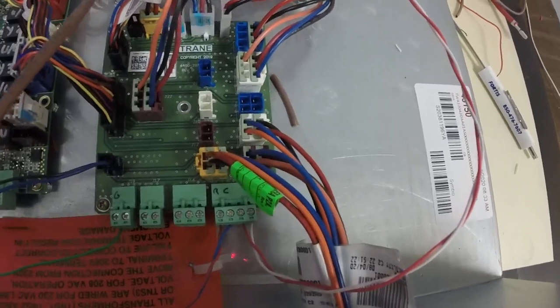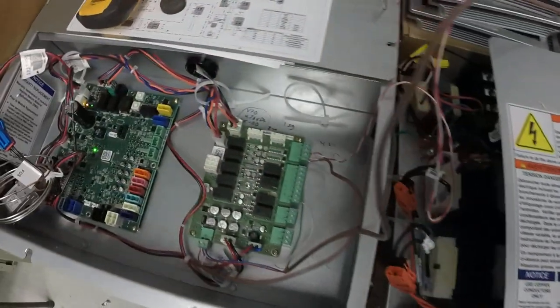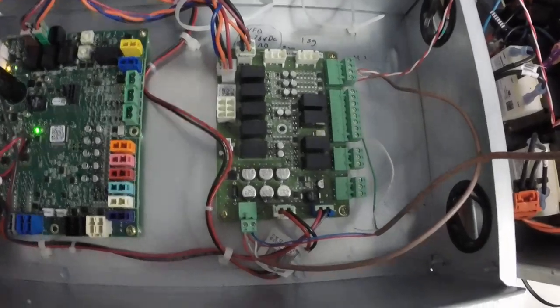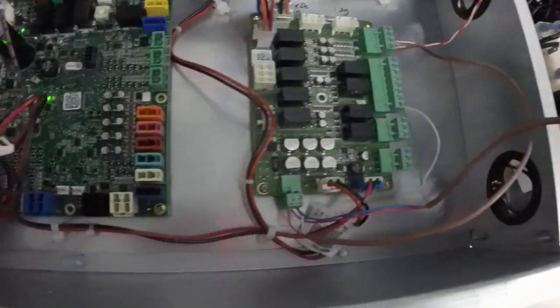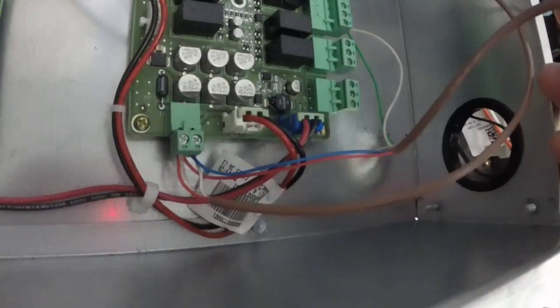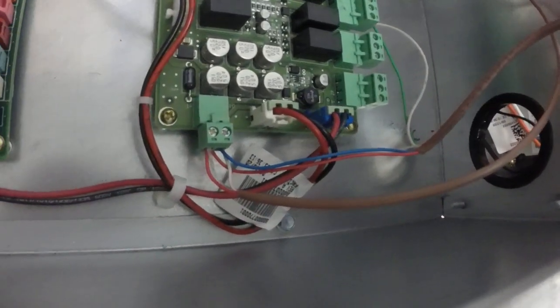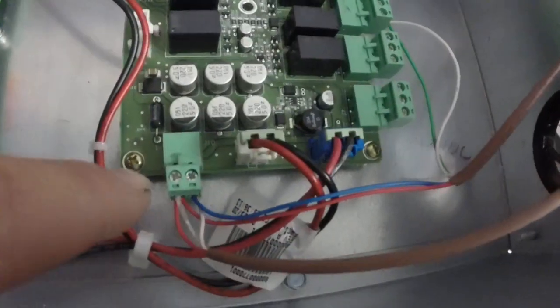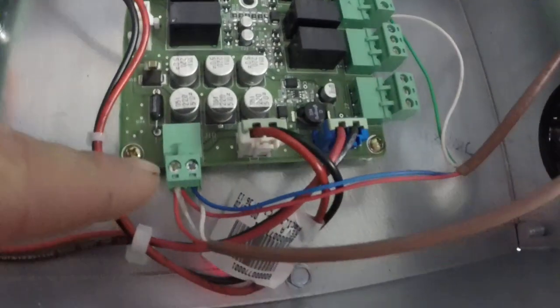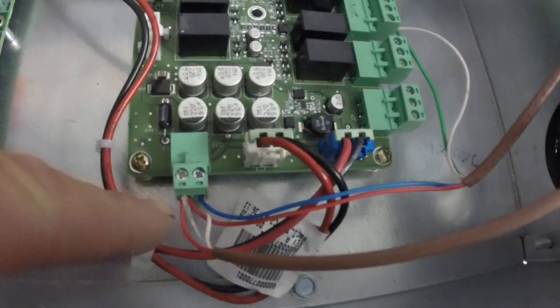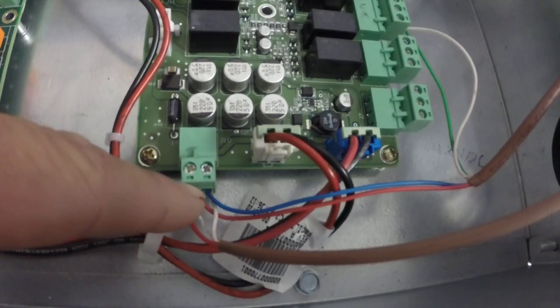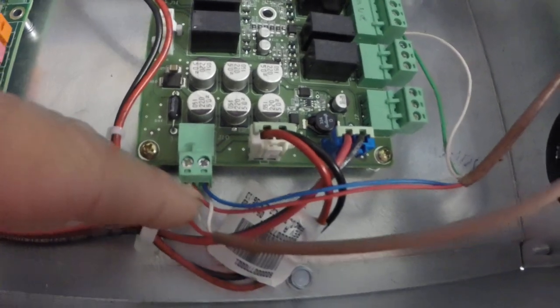All these conductors will go over here to the air handler portion of it. So if we look at that, this is my wire with the four conductors on it. Power coming off the J10 terminal. Pin one is hot, pin two is common.